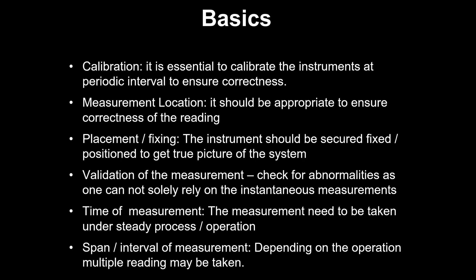So this again needs to be assessed. Similarly, when we are doing a power measurement for a chemical plant reactor, the load keeps on varying, depending on the total contents in the vessel, the viscosity and temperature of the material, and other things. The power drawn by the drive can change. So we have to do the measurement at normal or full operating conditions. Sometimes we do it at two levels, minimum, average and maximum, so that the suggestion can be made accordingly. There are now voltage optimizers and star delta converters available, so the correct suggestion can be given, and they can actually get the saving.